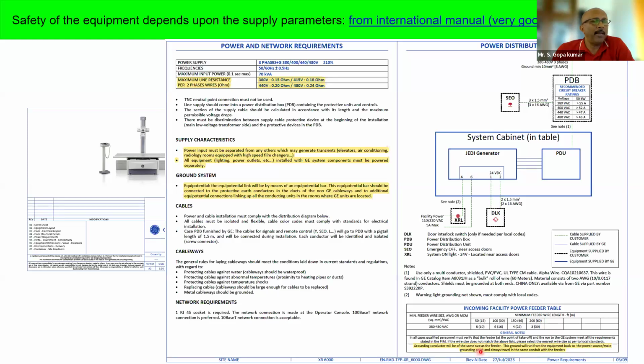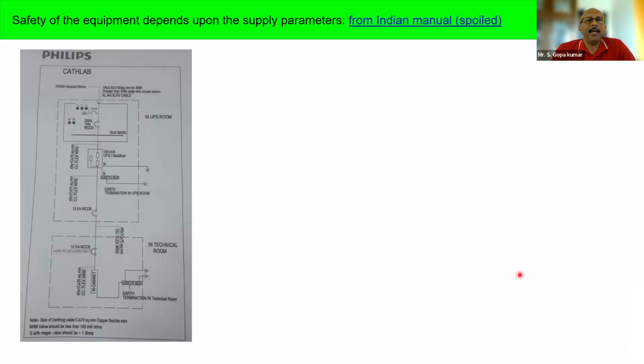Source main grounding point, that means the neutral grounding point of the system, and always travel in the same conduit with the feeder. This is the correct and perfect method of making a connection. On the other side, I am showing the manual from an Indian manual.